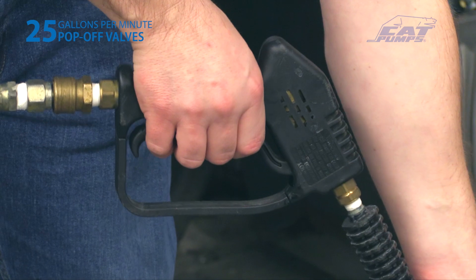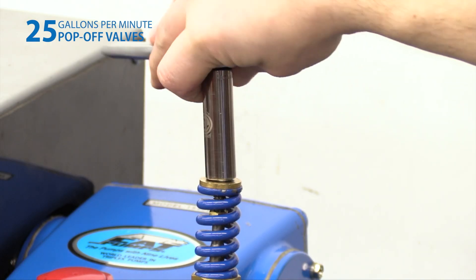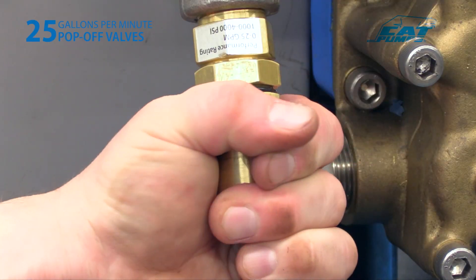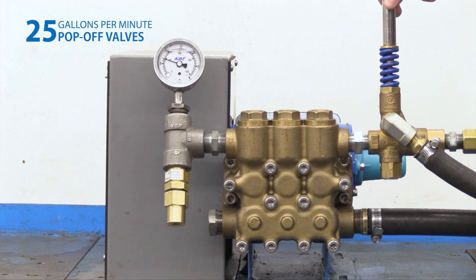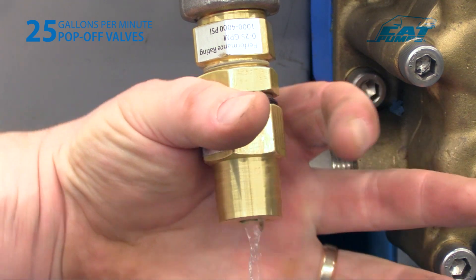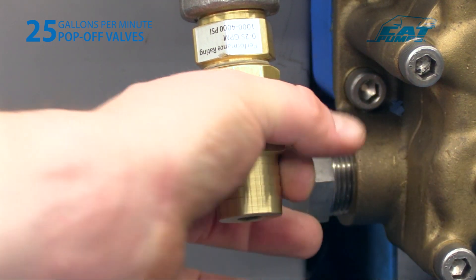With the system on and running, actuate the flow downstream. Adjust the primary pressure control valve clockwise to increase the system operating pressure to the desired setpoint. If there is visible water coming from the pop-off valve bypass port during this process, continue to increase its setting. With the system operating at full pressure, slowly turn the pop-off valve's adjusting barrel counterclockwise until a small amount of water is dripping from it. Adjust a half turn clockwise until dripping stops. No more than three half turns should be required.